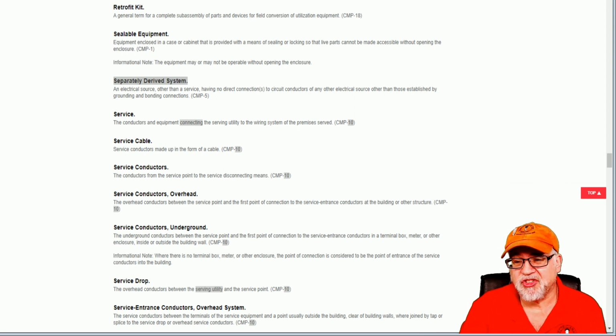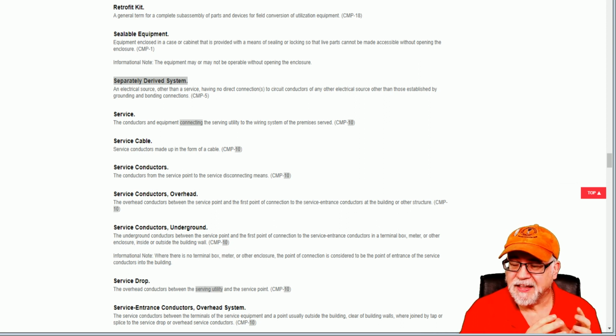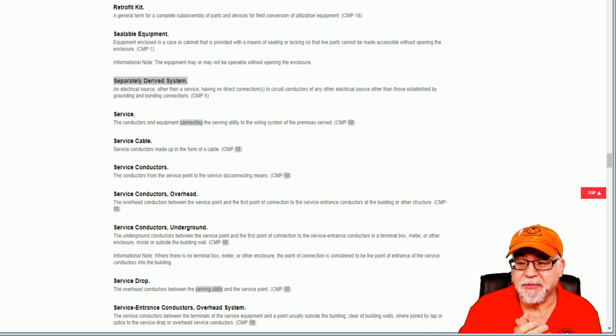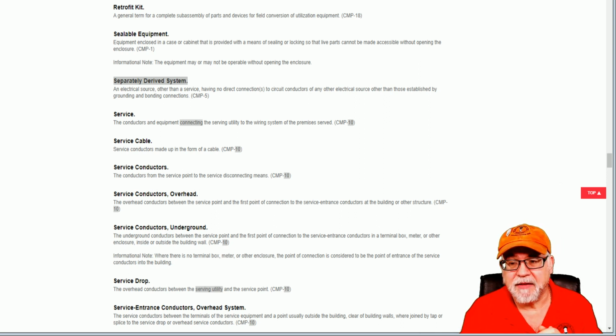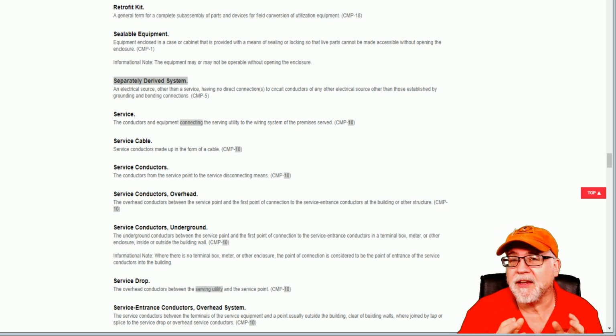Now, let's talk about generators. So generators, where you have a generator that's outside. It doesn't matter whether it's emergency, it doesn't matter whether it's legally required, or it doesn't matter whether it's optional. Typically, optionals are not going to be separately derived. But in many cases, emergency ones or legally required could be separately derived. Now, why is it important to know the difference? Well, all of this is based on the transfer switch.